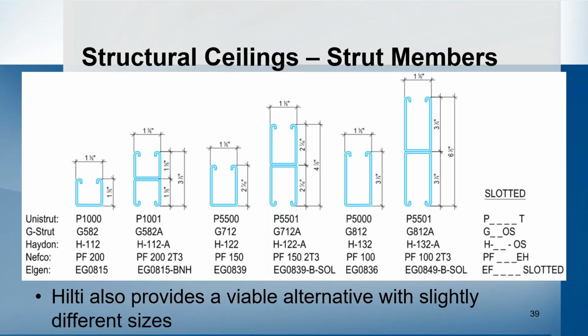And then typically any of these come in a slotted. The slotted has some different nomenclature depending on who the manufacturer is. And slotted, we've seen from data center to data center, slotted may or may not be required. Sometimes it's a requirement, sometimes it's not permitted. So that's something also to look out for, whether or not it's permitted or required, because it affects connections, whether you have slotted or unslotted, and it affects the capacity of the strut as well. And then also another manufacturer is Hilti. They also have a strut member as well that has slightly different sizes than what the typical strut members have.